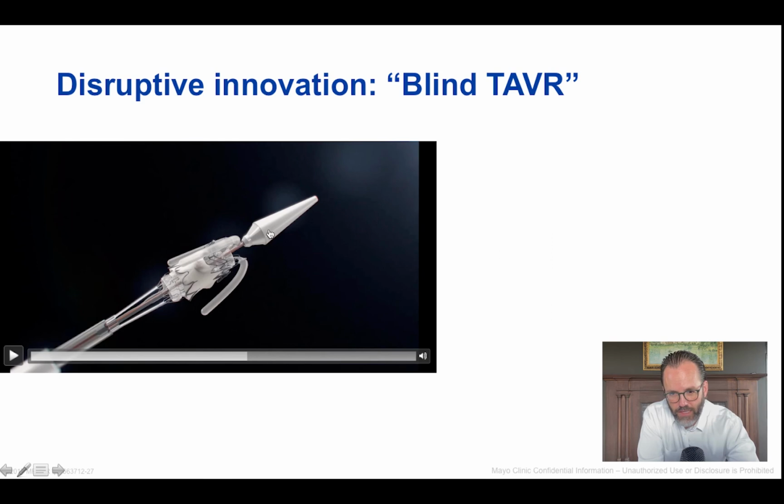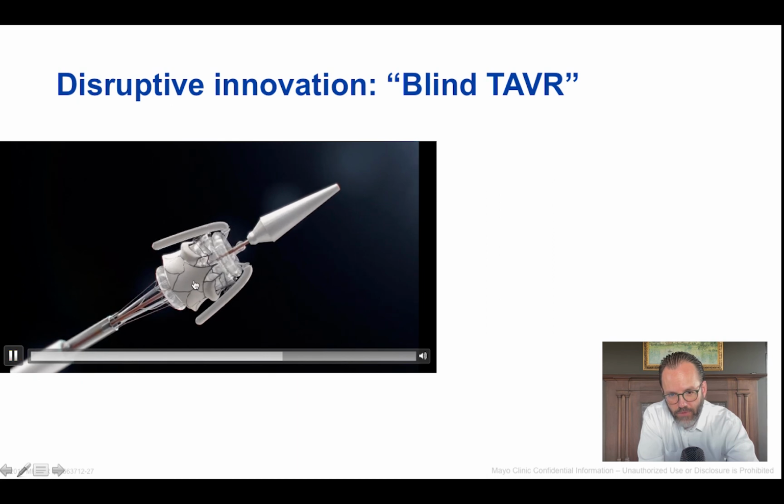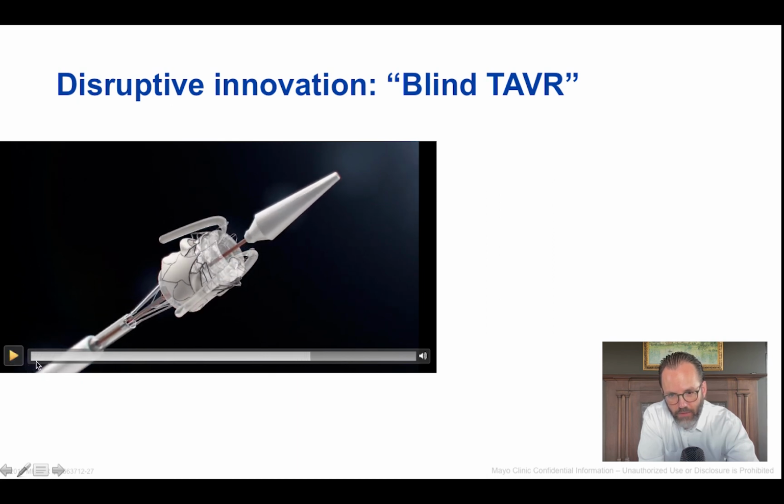The interesting thing is that these hooks, once this is inserted through the aorta into the aortic root, can be deployed and pulled back to confirm seating of the valve deployment structure in the appropriate position, and then subsequently you can have deployment of the valve structure with the inflation of these balloons.